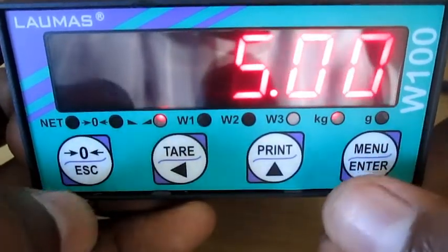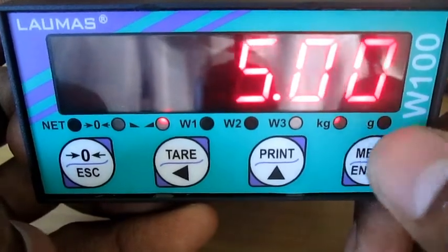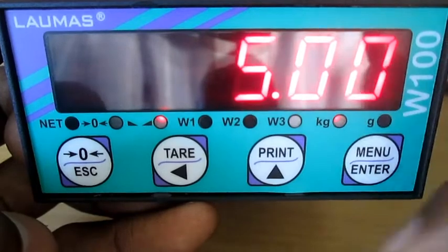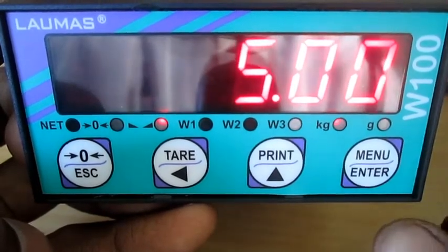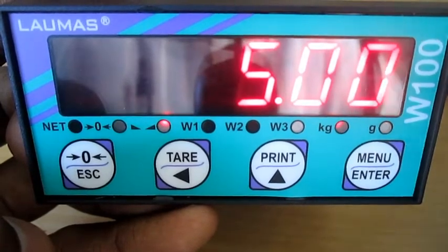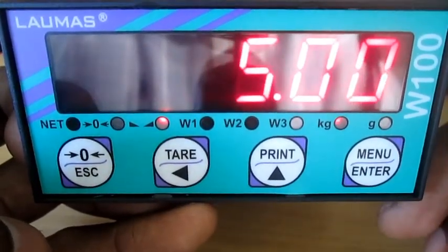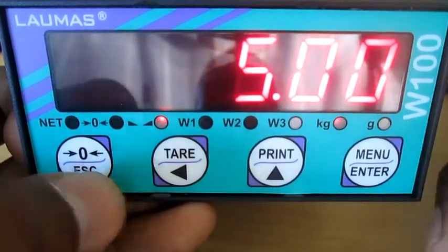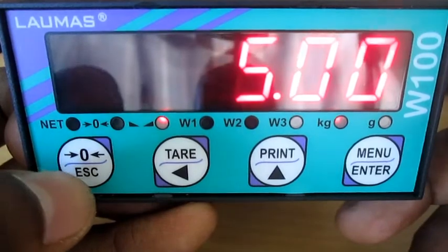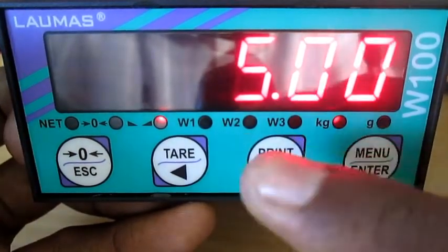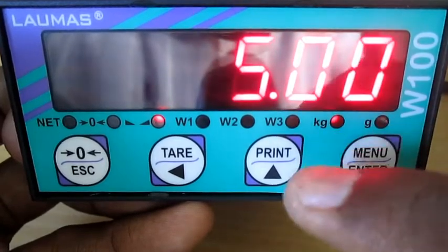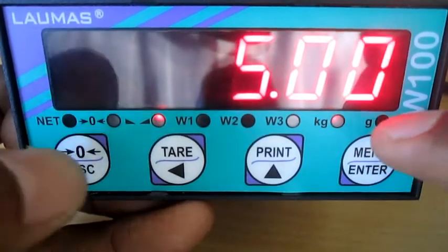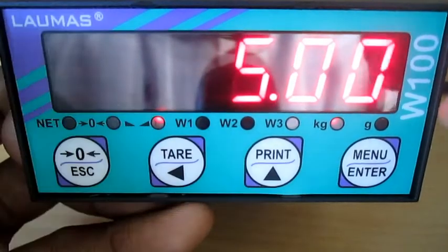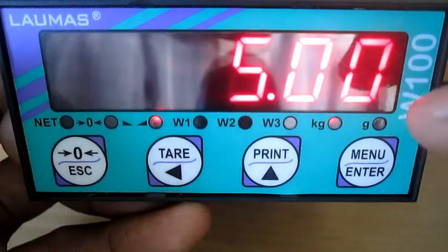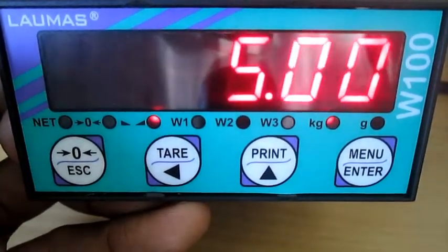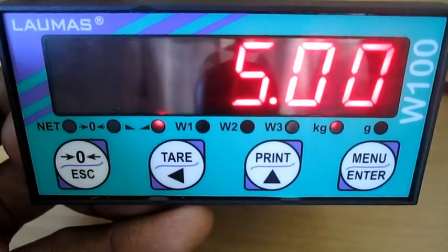Okay, and you can see apart from this kg unit indication, kg and grams, there is W1, W2, W3. By default this W1, W2, W3 is for relay output indication, but that will not happen at present because we have not enabled that function. So at present this will be working as primary functions. Primary functions display only unit indication and then gross, net, tare indication and stable weight indication. Only these 5 outputs come to primary functions.